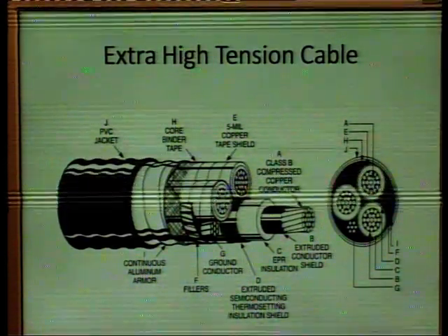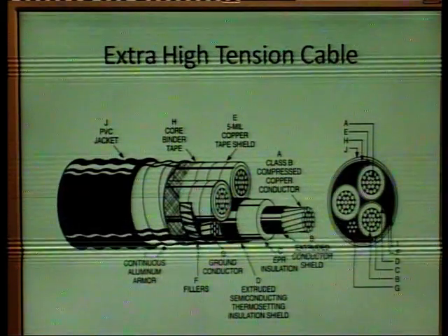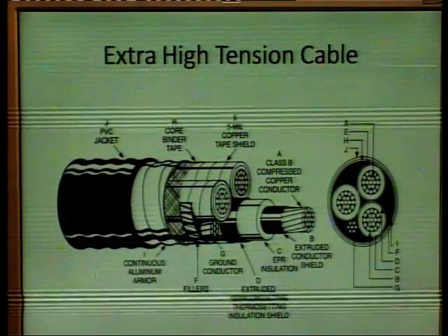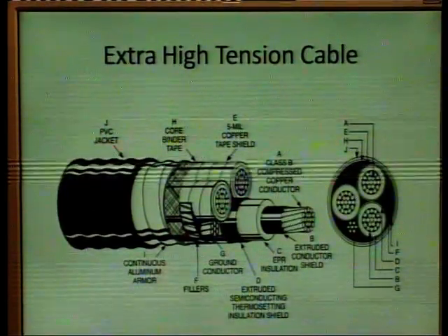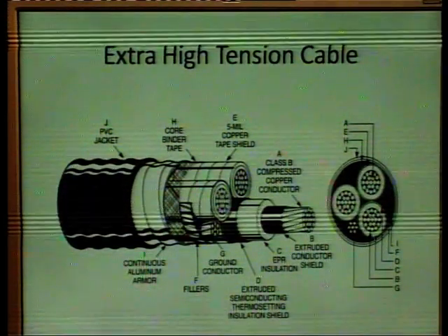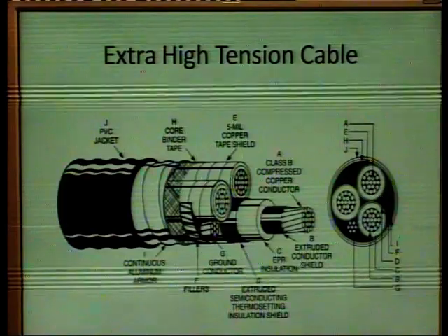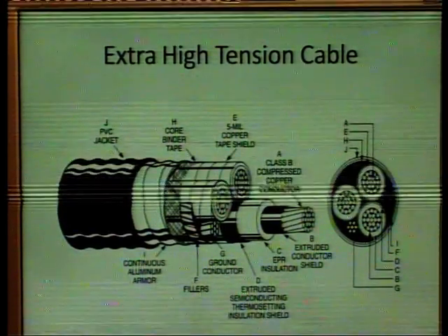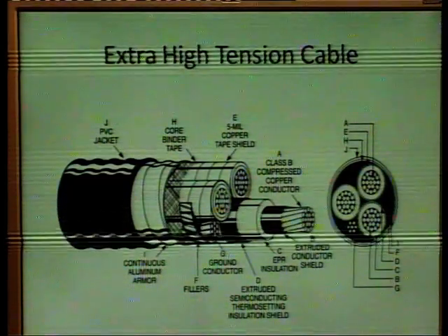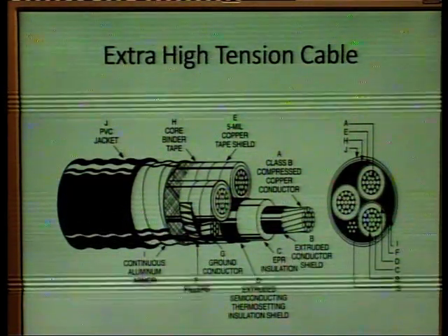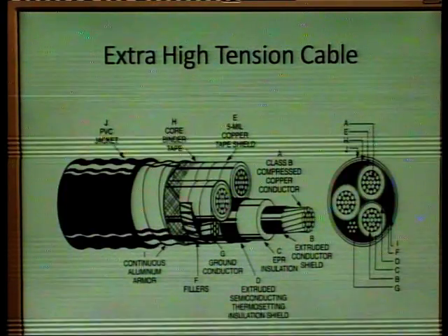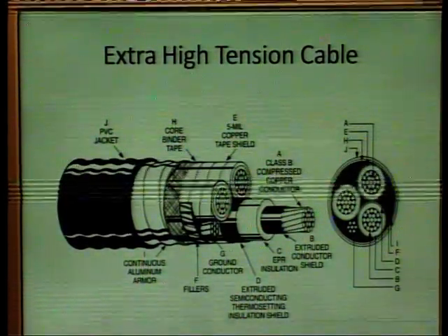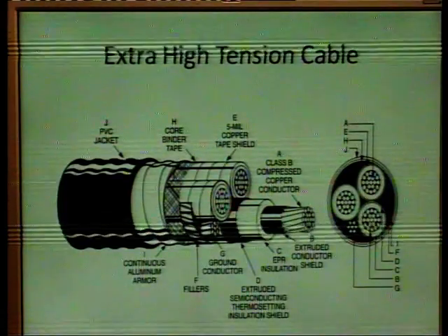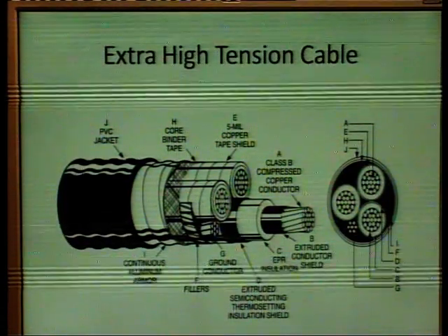fillers are there, ground conductor is there, copper tape sheath is there, and class B compressed copper conductor, extruded conductor sheath, EPR insulation, extruded semiconducting thermosetting insulation shield is there. So this is the extra high tension cable.